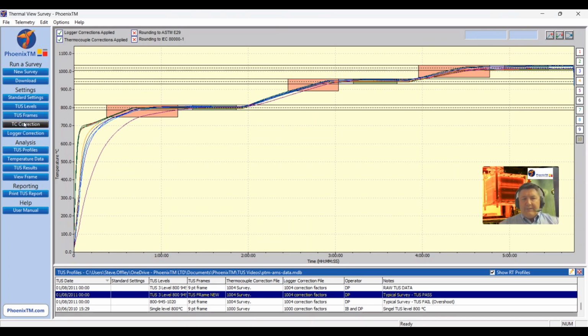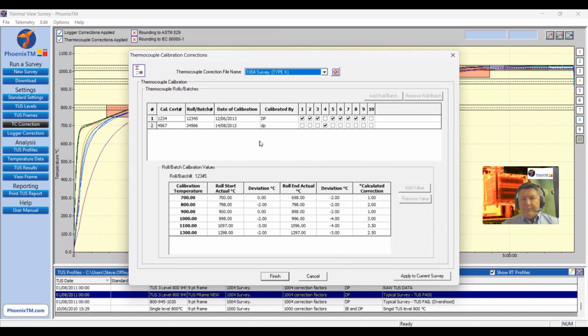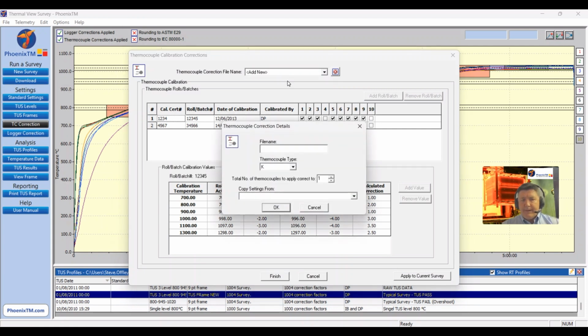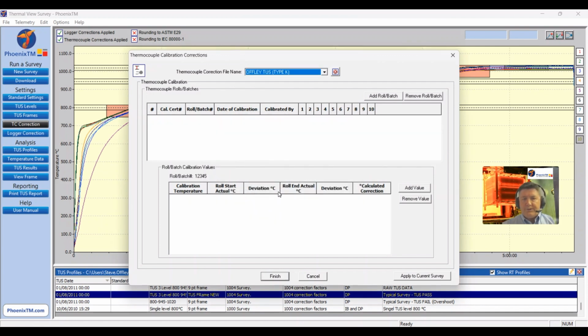So how do we create a thermocouple file from scratch? What I'm going to do first of all is go to the file library header and go to, as convention has it, add new. I'm now going to choose my file name, so I'm just going to call it Offley TUS. I've got a type K thermocouple, and I'm going to use a 10-channel data logger, so I'm going to apply 10 channels here. I could pull back a historic calibration file and edit that, but I'm not going to, so I'm going to click on OK to create a new file altogether.